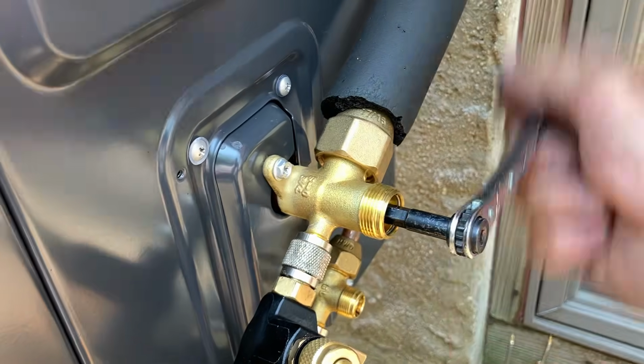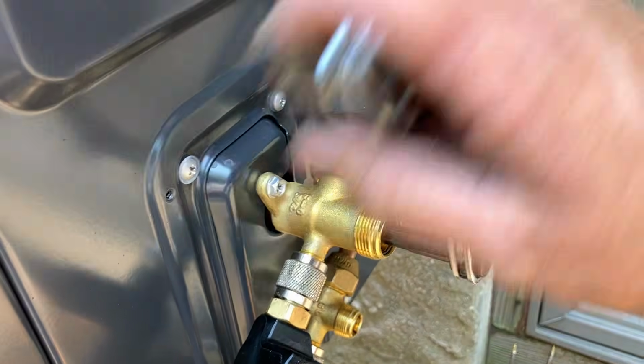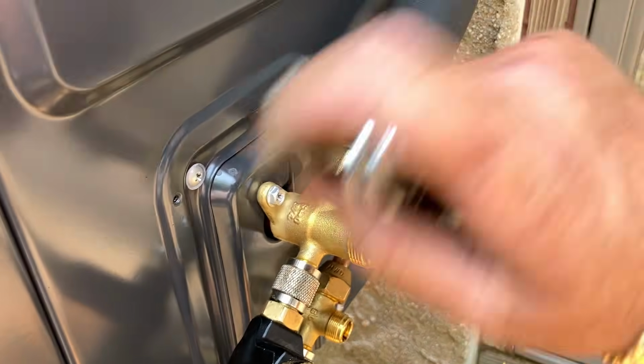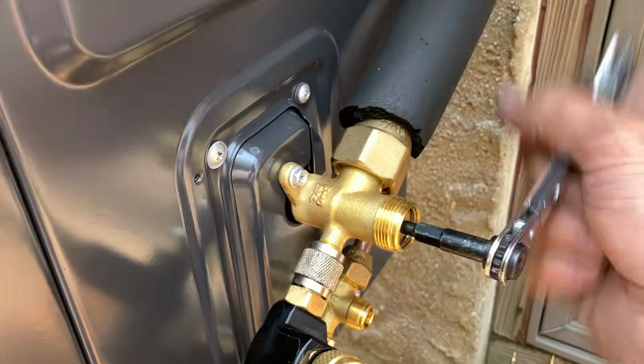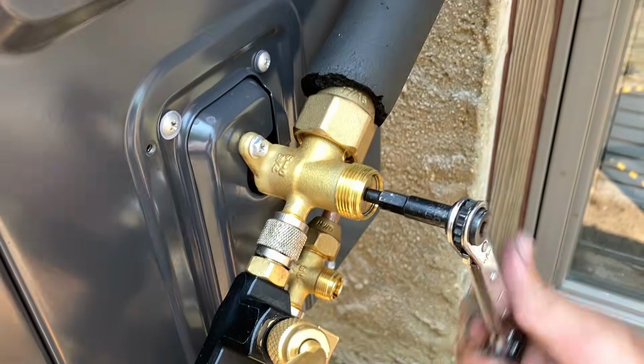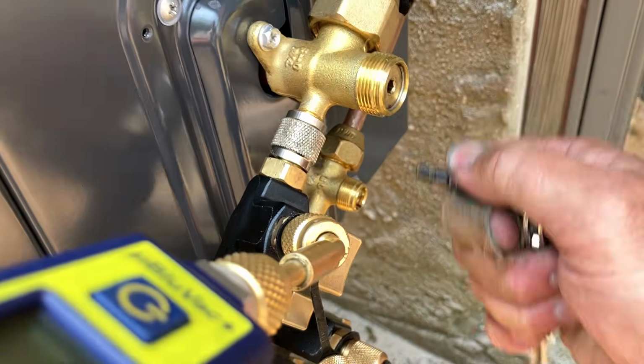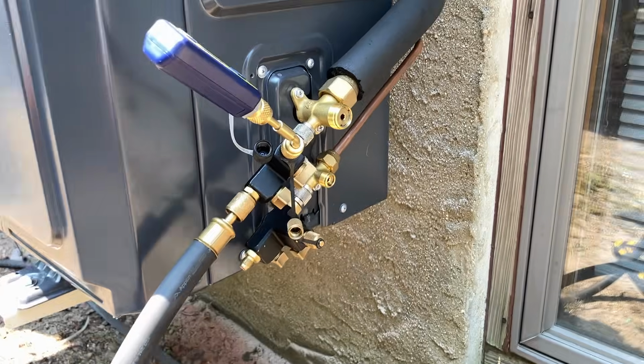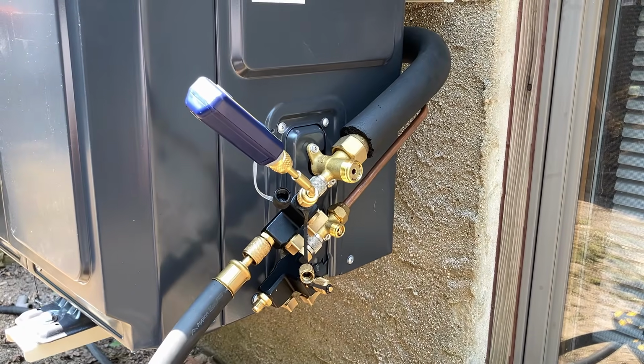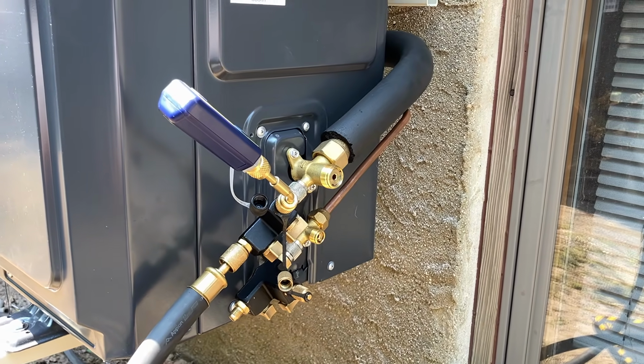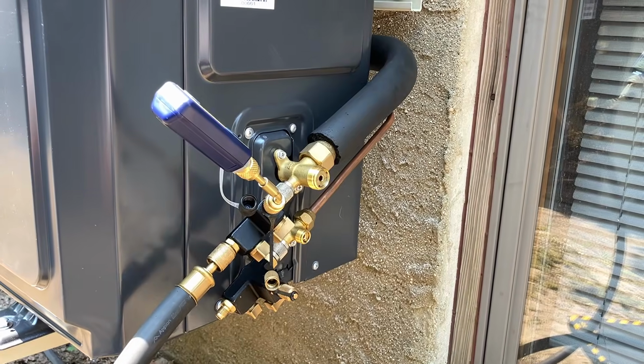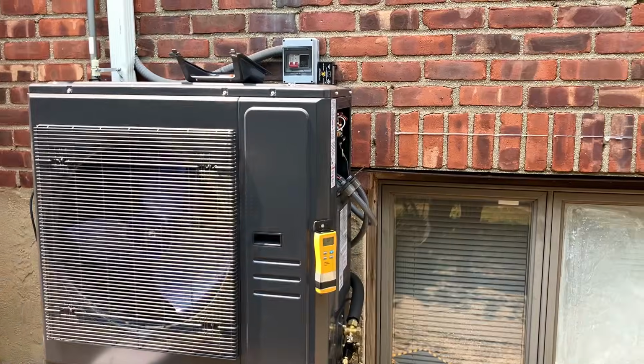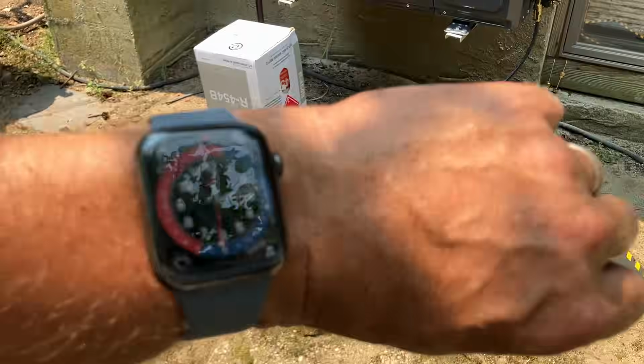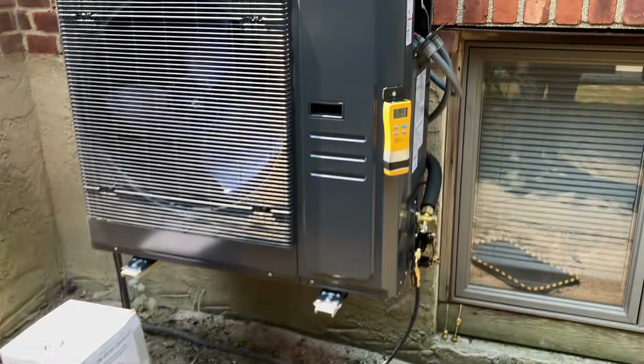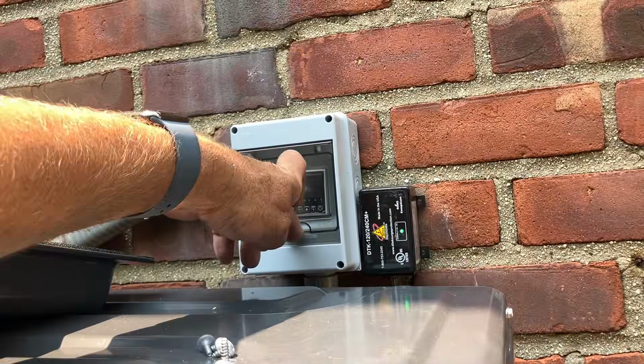So now I am opening up the low side service valve that is connected to that 3/4 inch line, also known as the suction side of the system, right to that retaining clip right there. Wiggle that out. So now the line set is charged. All we need to do now is calculate our line set and add the proper amount of charge to that system so we have the right amount of refrigerant. All right, 13 minutes after 12. Let's turn on power.